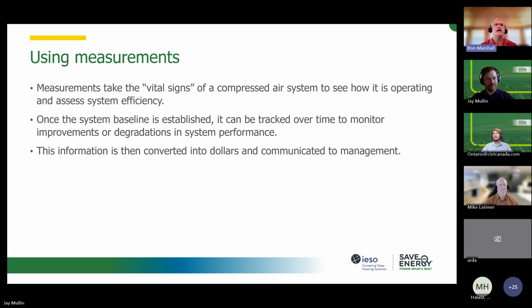You can see if you're tracking baseline or having your system measured, if it's getting better or getting worse. And then you can use the money to convert the savings or additional costs into dollars and communicate to management, right? Perhaps you do something simple like fixing leaks and optimizing the compressor control by adjusting the set points. If that saves quite a few thousands of dollars, you can report that to management and perhaps they'll trust you to do maybe something a little bit more expensive, right? And get further savings.